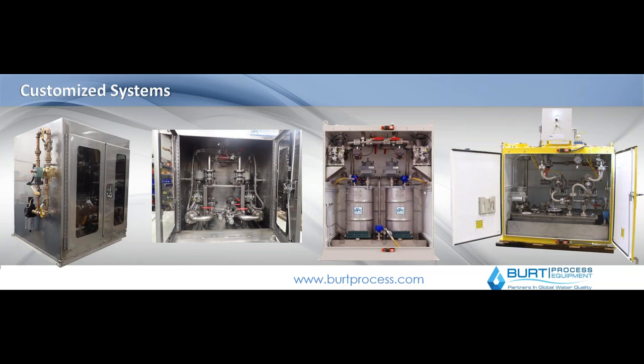Chemical feed systems can also be utilized for hazardous chemicals — in this case solvents or isopropyl alcohol injection, which is very common in the semiconductor industry. These are built into fireproof cabinets with chemical injection, 55-gallon drums, poly stainless steel cabinet, Class 1 Div 2 or Class 1 Div 1 rated, with air-operated diaphragm pumps and conservation vents located in the system. Larger versions move into more of what could be called solvent-based injection, looking at some more of the different solvents that can be utilized as well.